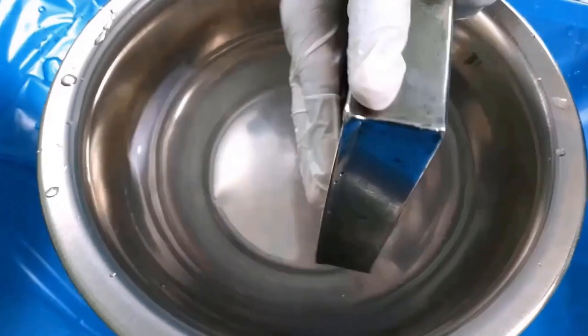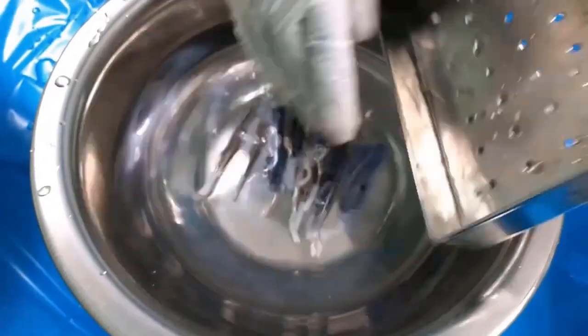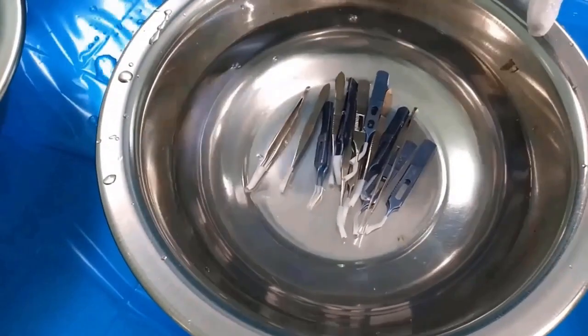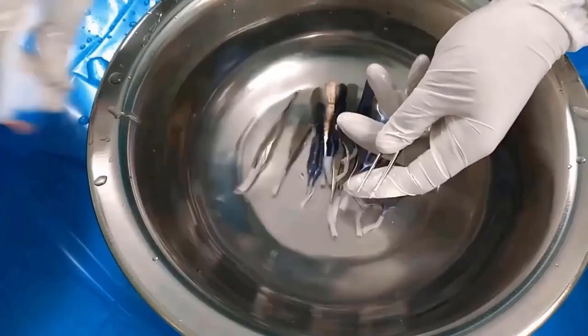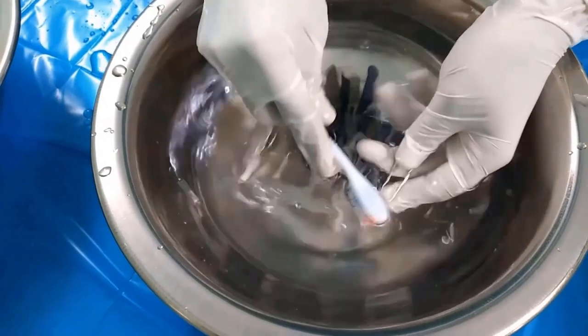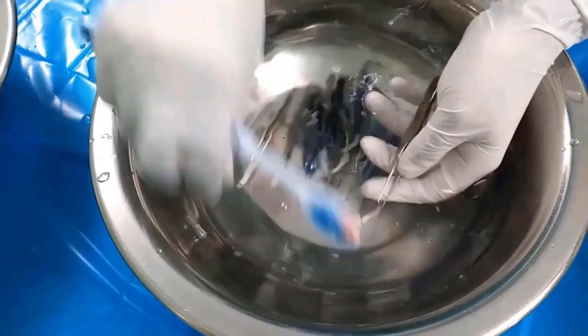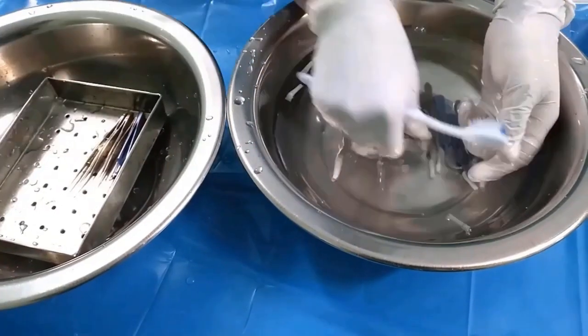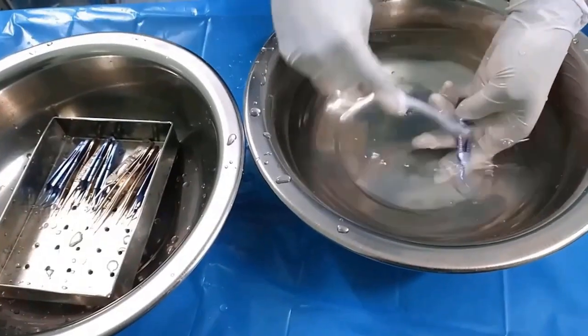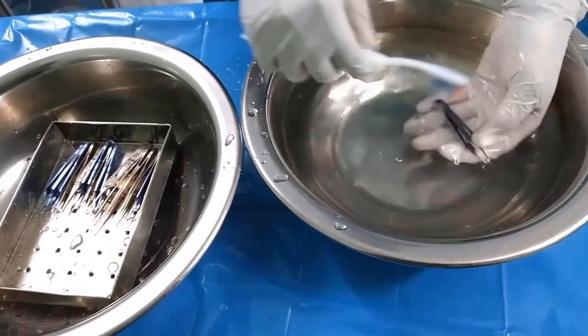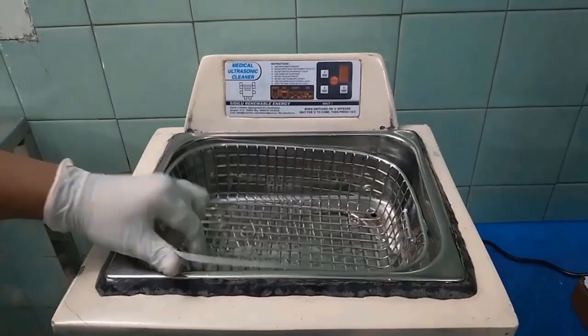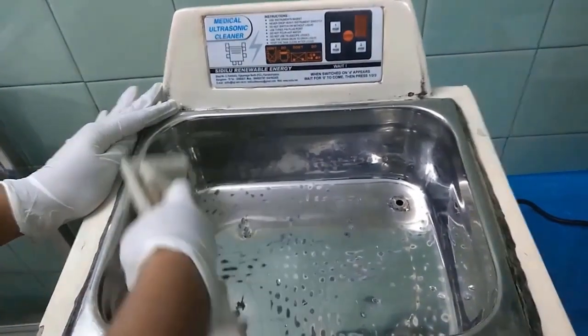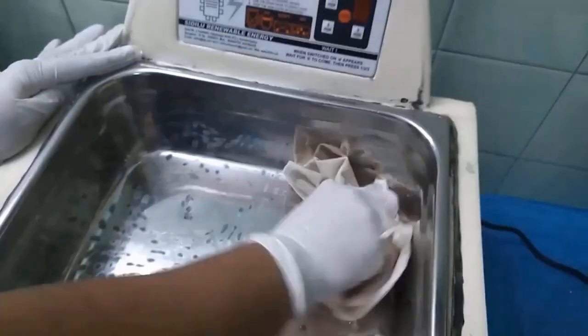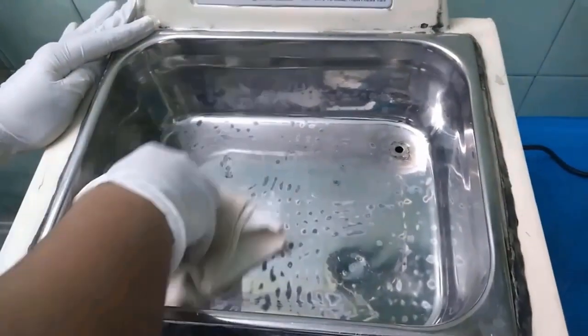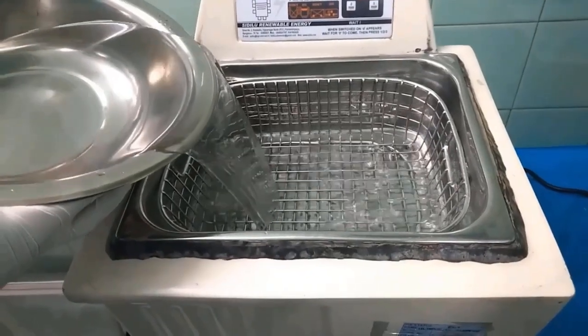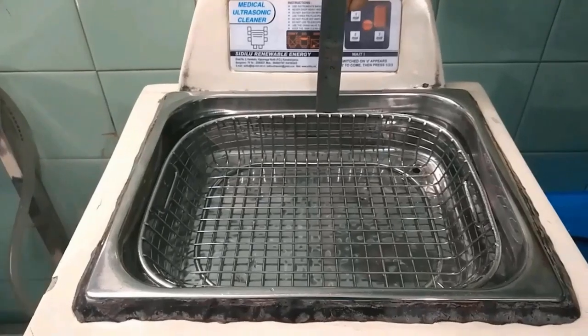Before washing instruments, wash hands thoroughly and wear OT dress with cap, mask and gloves. The instrument washing room should be clean and air conditioned. Before putting into the ultrasonic cleaner, all instruments should be washed in separate basins. Ultrasonic cleaning: fill it with the correct amount of water, because it should not be overfilled or underfilled.